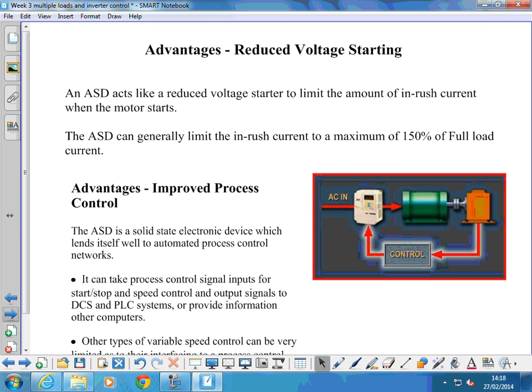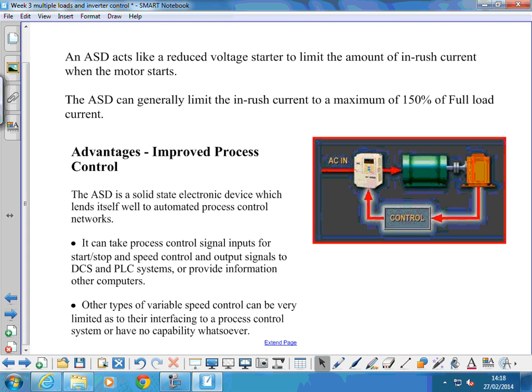Also, improved process control. Solid state electronic devices lend themselves well to automated process control. This is where we'll have some kind of sensor feeding back information about the speed of the motor to a control part that tells the inverter to add or reduce power to keep the motor at a constant speed or change its speed to some new value depending on what's going on with the process.